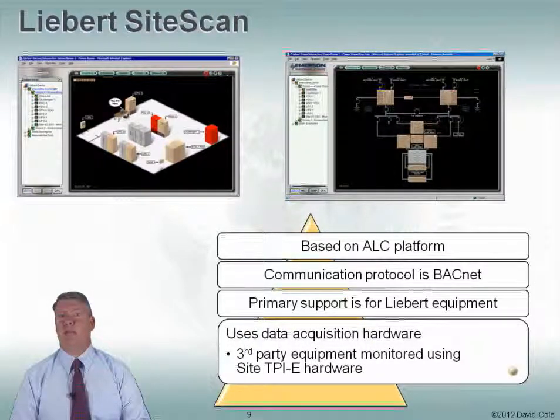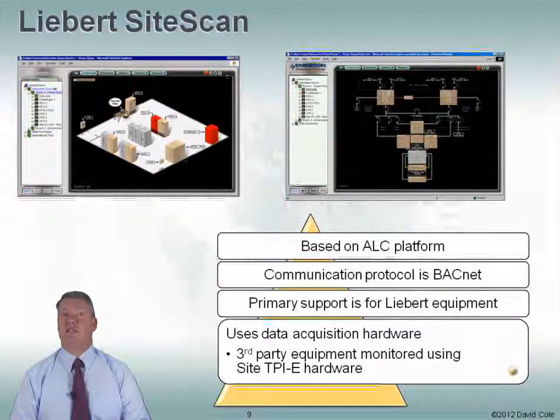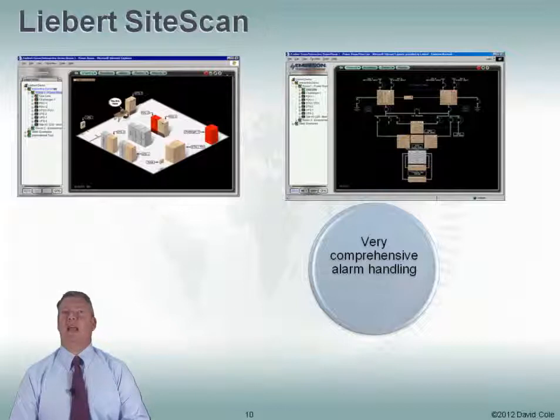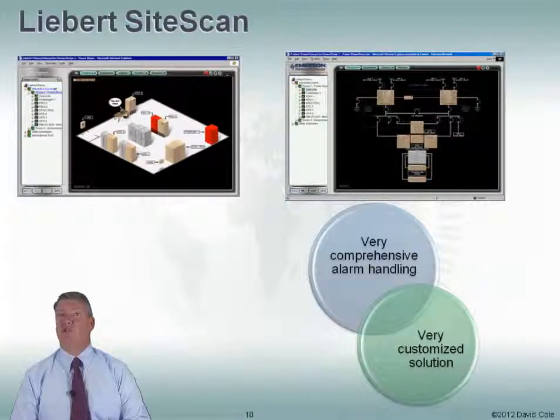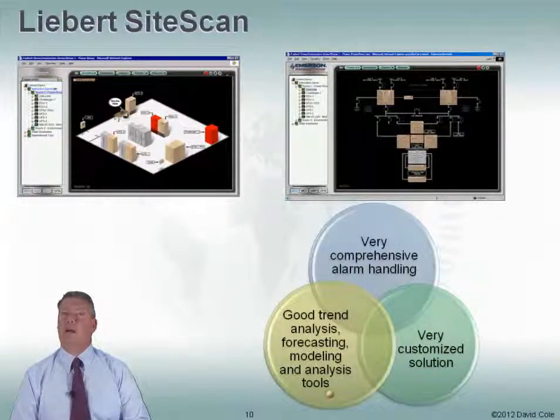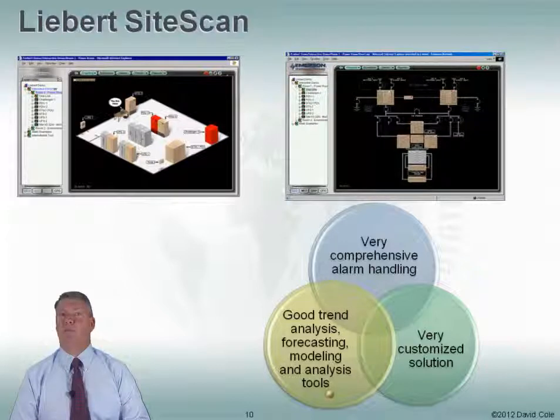In the case of Liebert SiteScan, they use data acquisition hardware. They've got third-party equipment that can be monitored using their Site TPI E hardware — TPI meaning third-party interface. They have very comprehensive alarm handling — they probably do a better job of alarm handling than any of the products out there, with an extensive list of things they can do with it. Liebert can be a very customized solution; the one-line diagrams and data center layout screens are all custom developed for a customer. They also do a great job of trend analysis, forecasting, and modeling, with some nice analysis tools included as part of the SiteScan product.